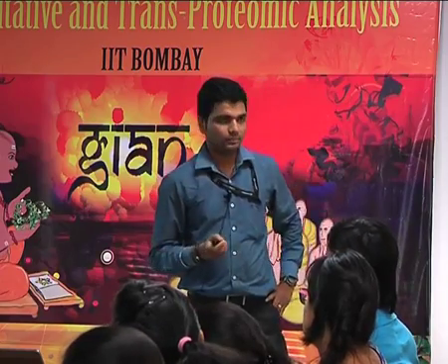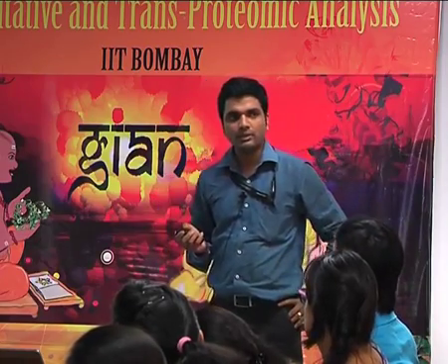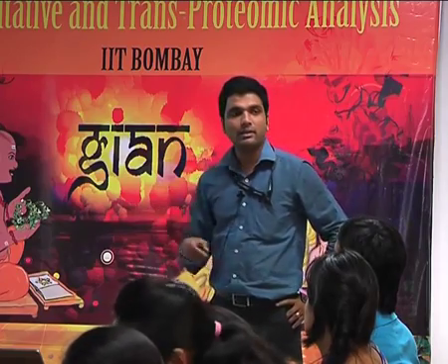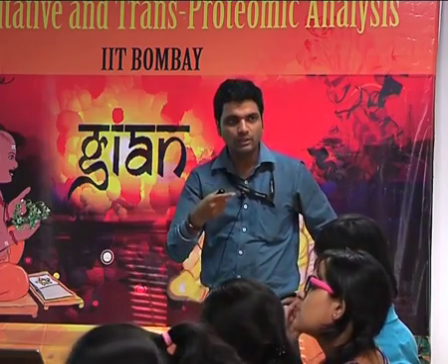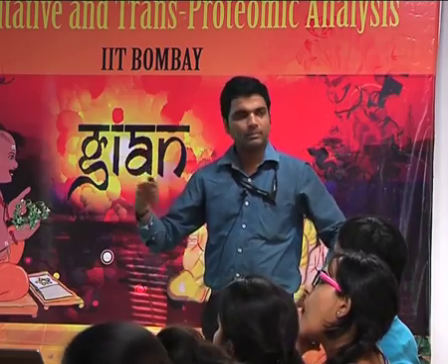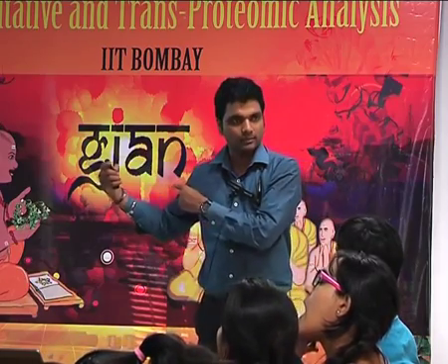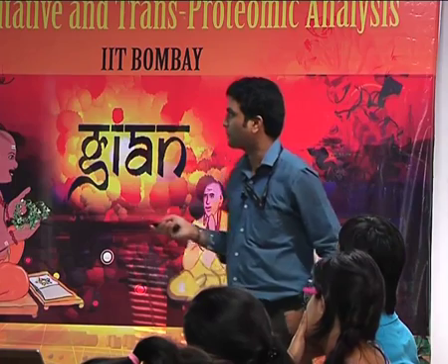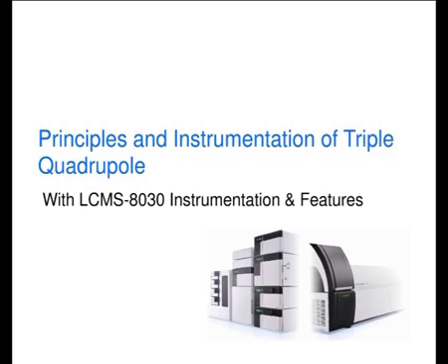The detector is an electron multiplier with conversion dynodes, where the ion strike generates electrons, and the electrons get multiplied and you get the results. Okay, you are getting the chromatograms. Just now we discussed the basic model, which is the single quadrupole. Now we are going to focus on the triple quadrupole.